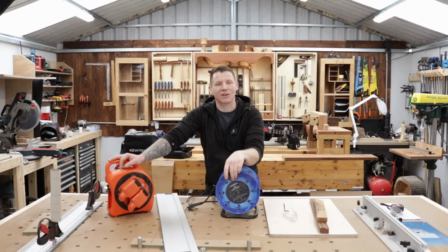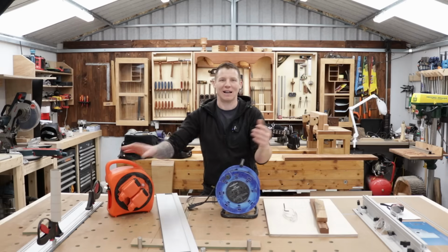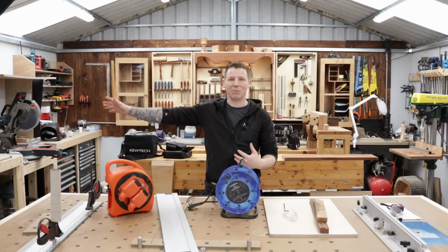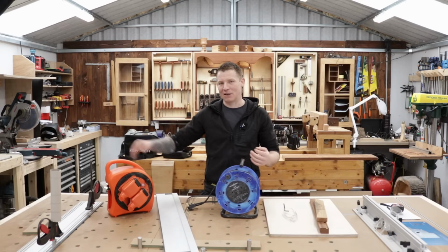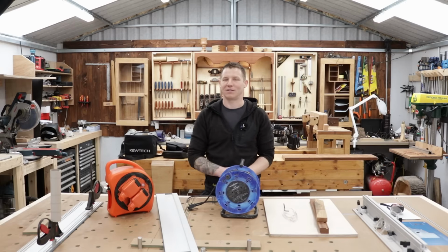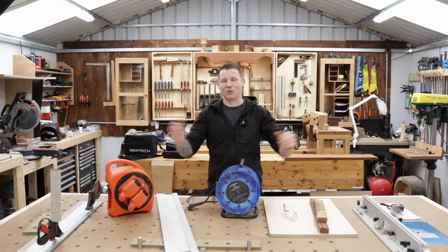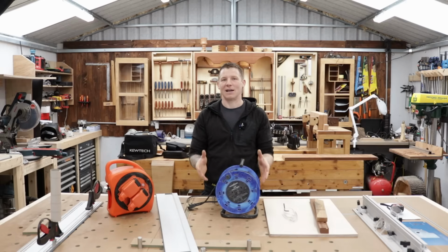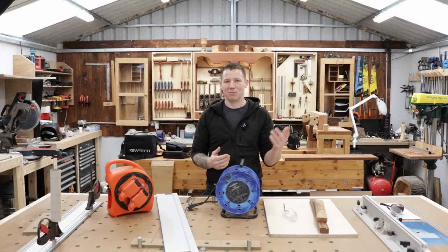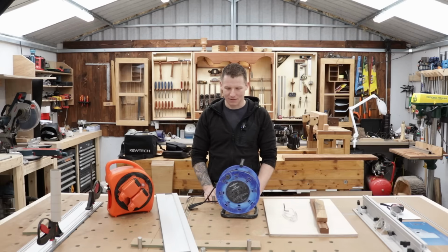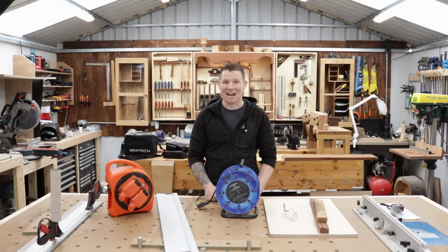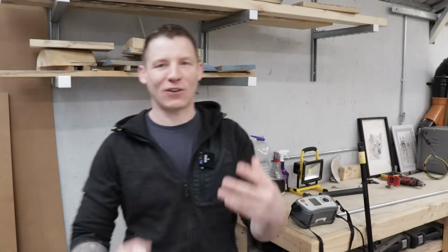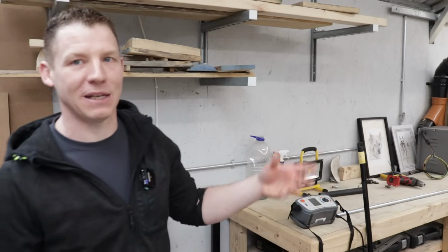Especially you guys, if you're into your gardening and stuff, you have a big long garden, maybe you have an electric lawnmower or electric hedge trimmers. They come with a big long lead as well. So you've plugged a big long lead on your trimmers into a big long extension lead. Now you're miles from your fuse board. You are not protected by the breakers in your board. If that thing shorts out, it's not going to trip the breaker. So it's just something to think about there. So let me demonstrate that for you with the meter, just how much resistance one of these things can add to a circuit.